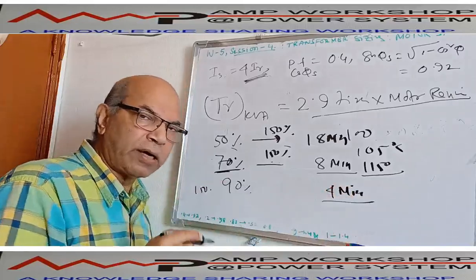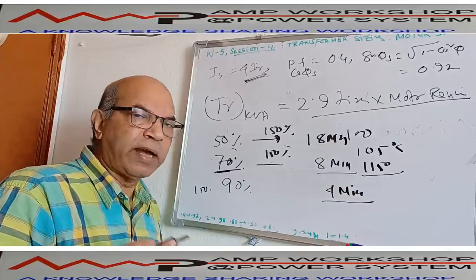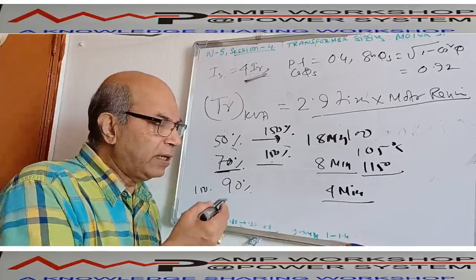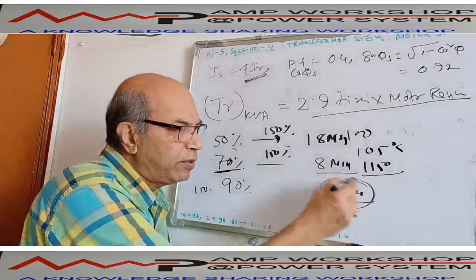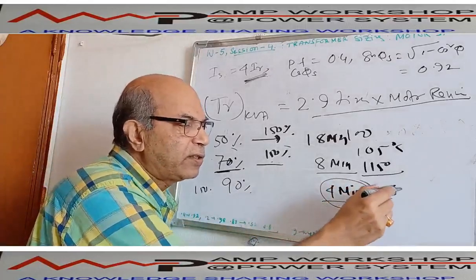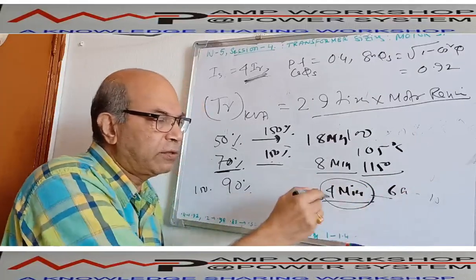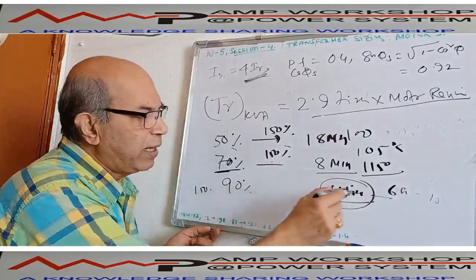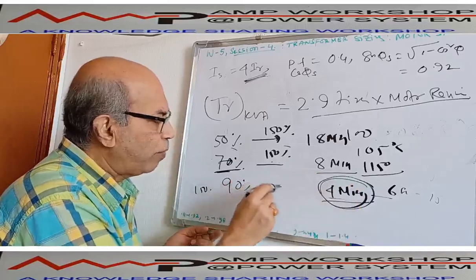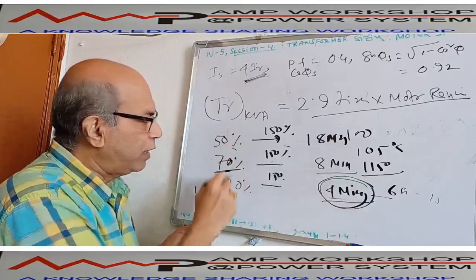So now in our case, when you go for the motor starting, the transformer has no load, frankly speaking. In that case, the motor starting time, how much? If we consider 4 minutes, it is only 6 seconds to 15 seconds. Nothing with this comparison. So easily we can load the transformer by overload by 150%, any of the loading.